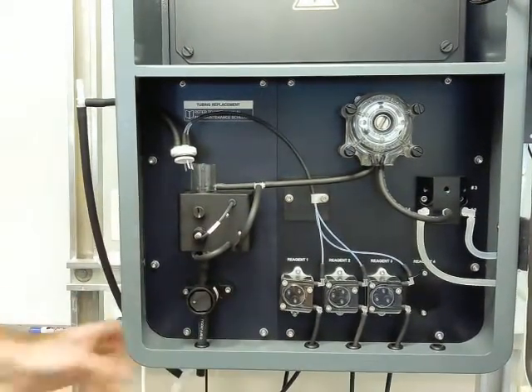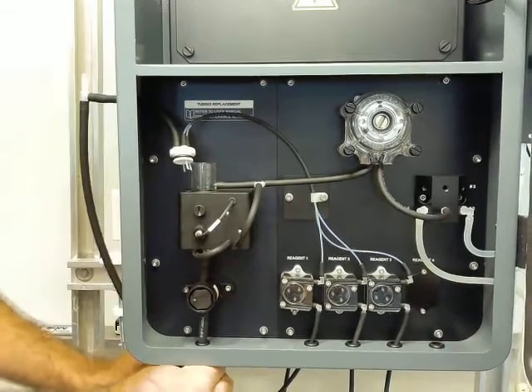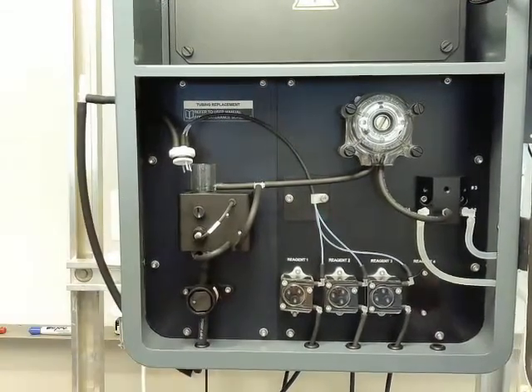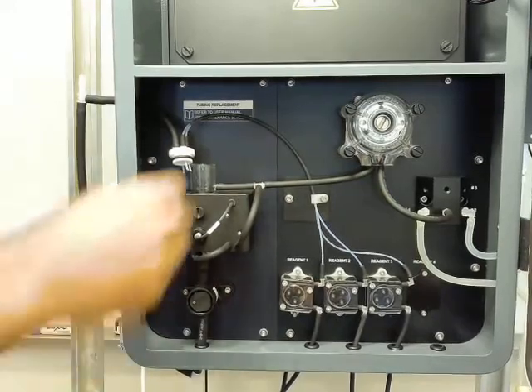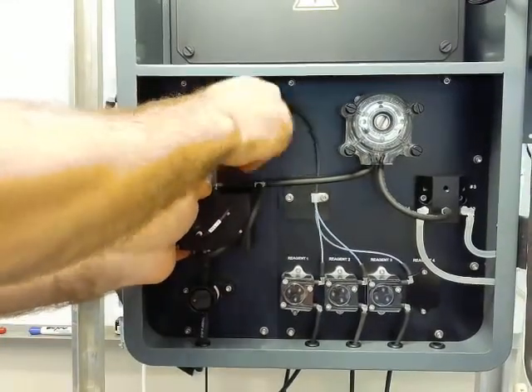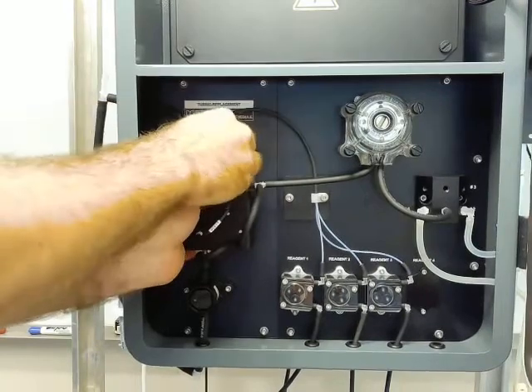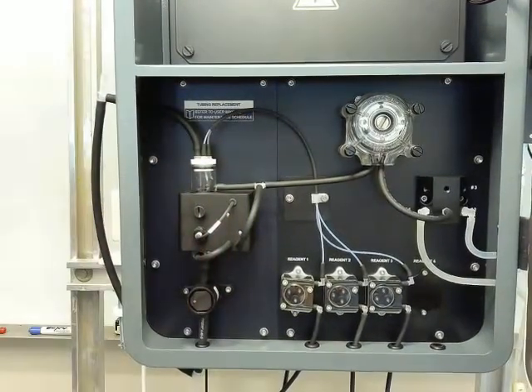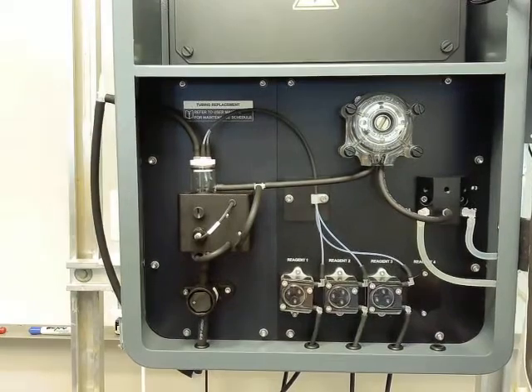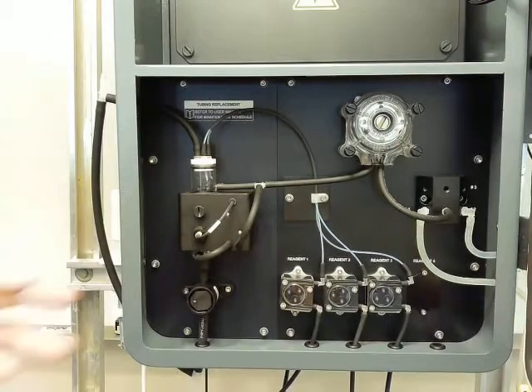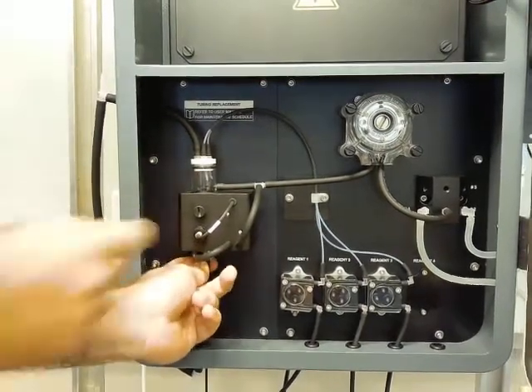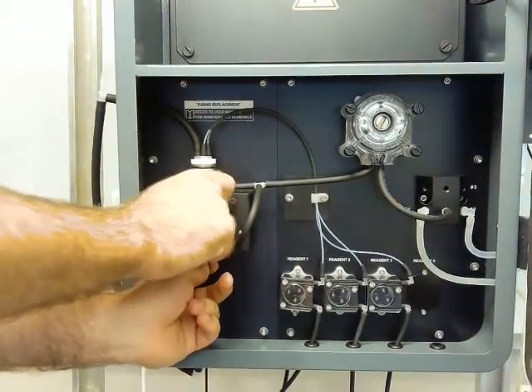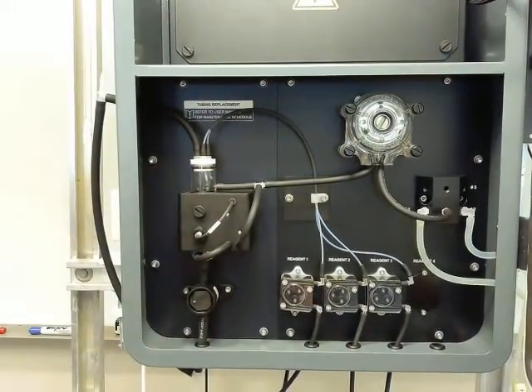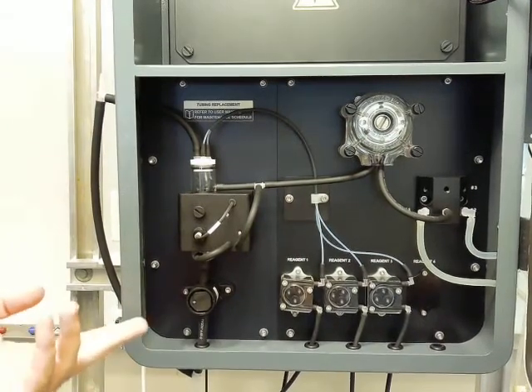Then we just go back to the bottom of the analyzer, reconnect to our drain overflow tube, and then put our flow cell cap back in place. Again, take a little bit of care. It's not a super tight fit, but anytime you're putting an O-ring into a glass cell, there's obviously a chance it could break should you use too much force or it doesn't go in neatly. And we just finger tighten our flow cell back into place, just so it doesn't get knocked around too much from vibrations or anything like that. And then that's basically our flow cell tubing.